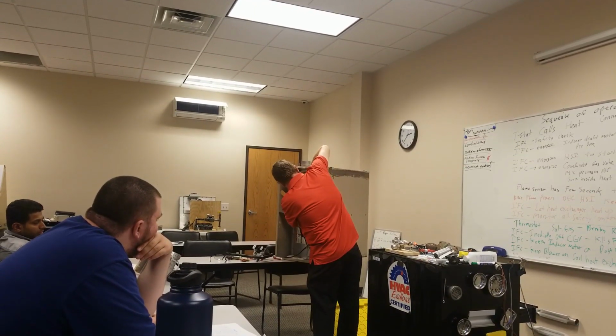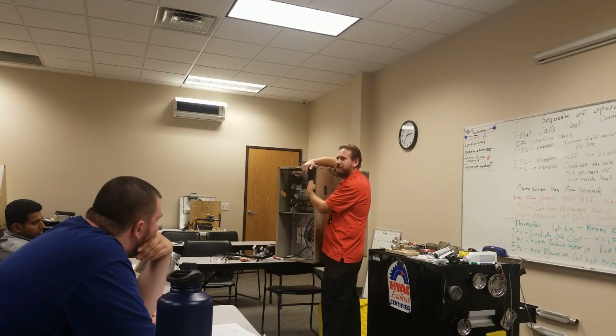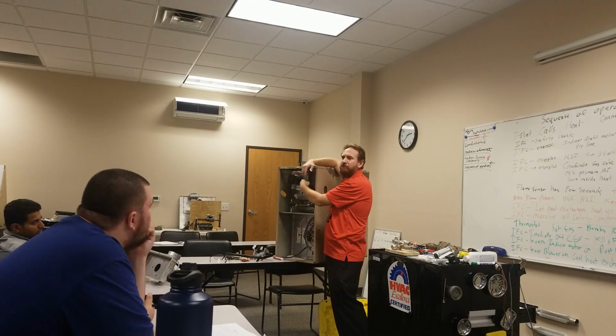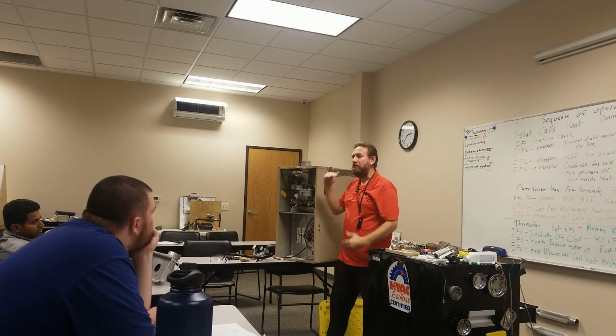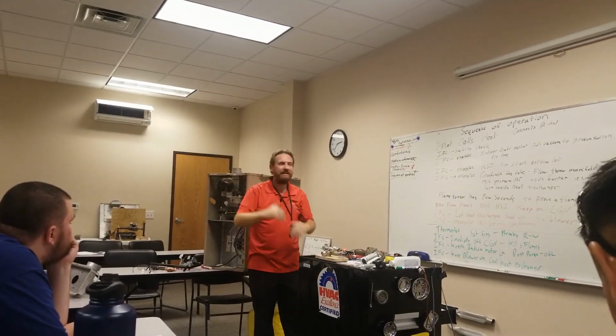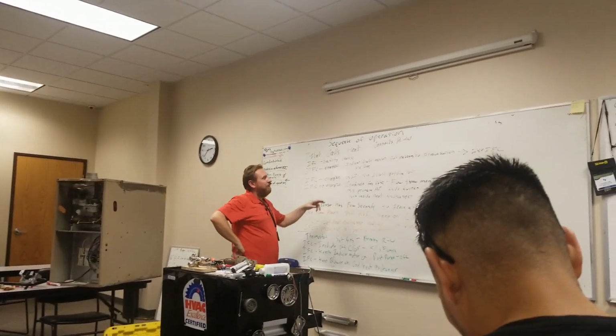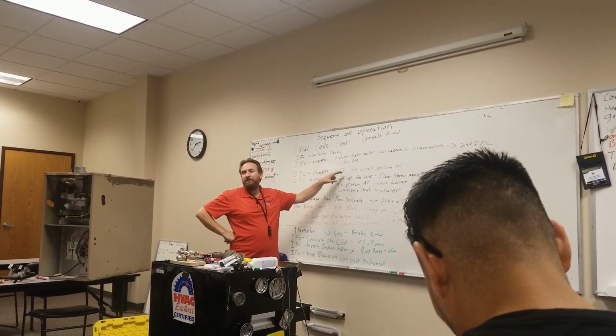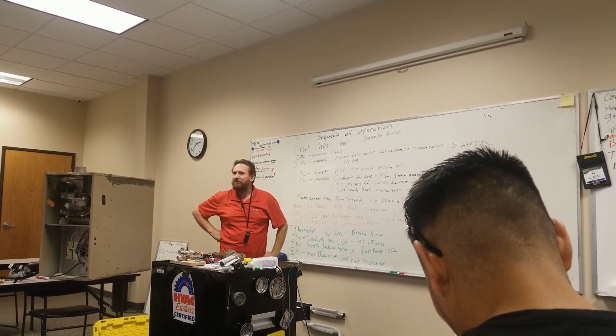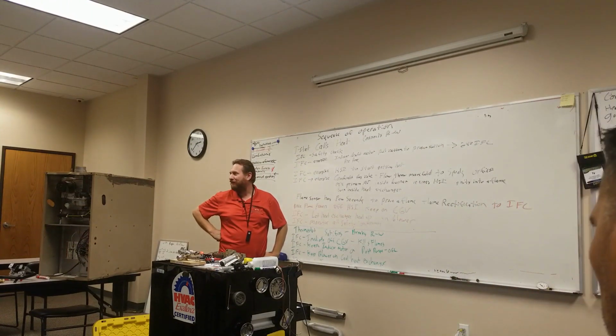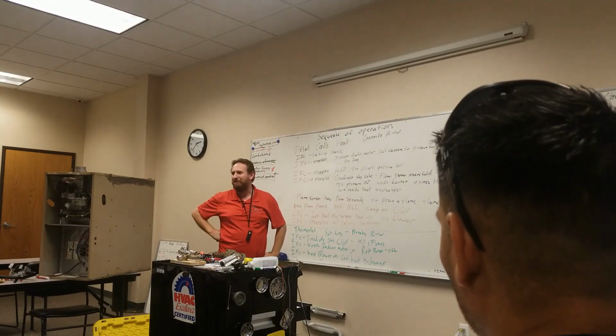Okay. Plug this back in. Check the pressure switch. Check the hoses to the pressure switch. All those things the pressure switch do. You know your problem is going to be in between that sequence. Or maybe it's not glowing hot, but you hear the gas valve go click, and you smell gas. And then you hear the gas valve click, shut off. What do you think the problem is?